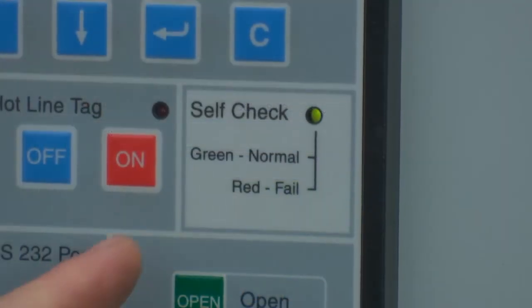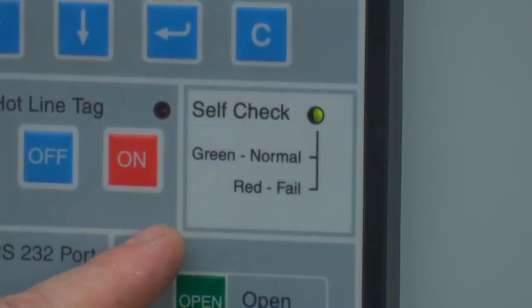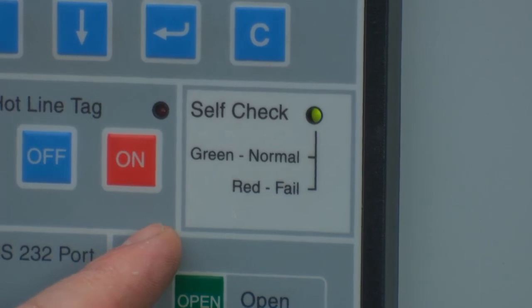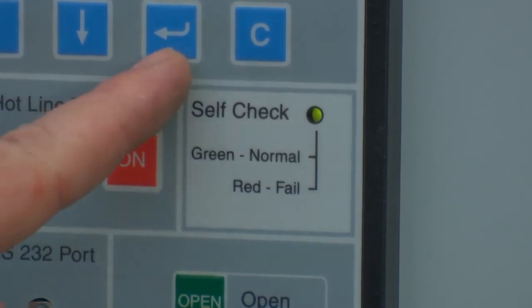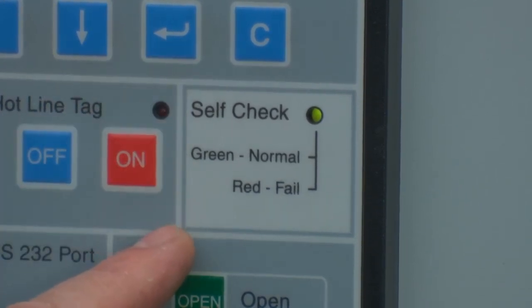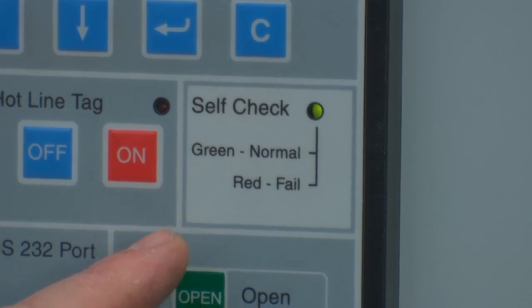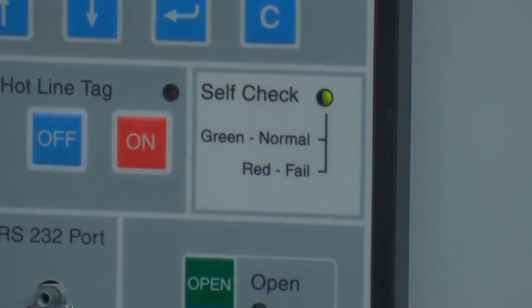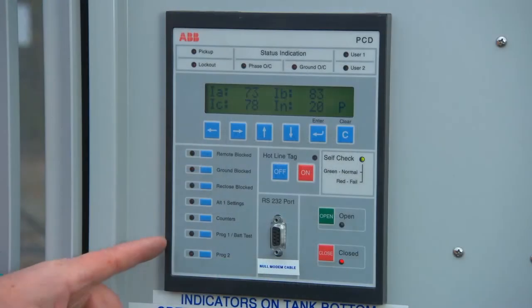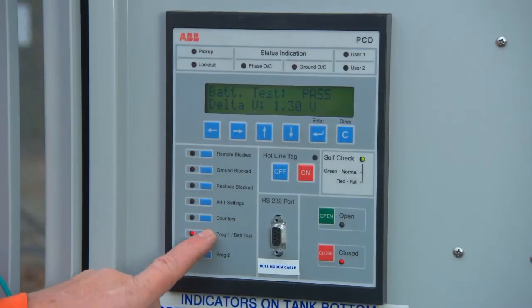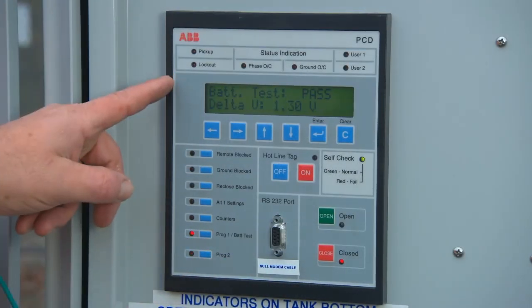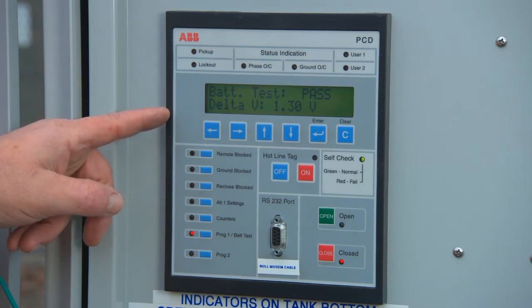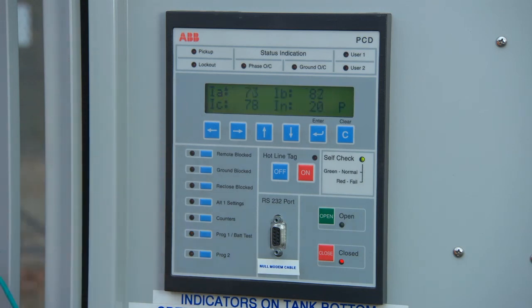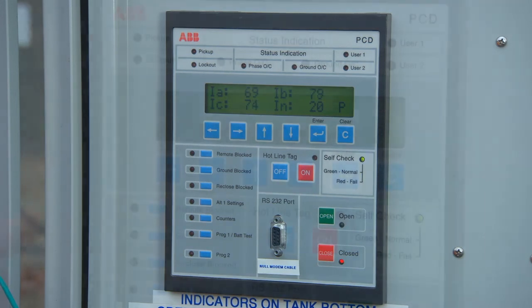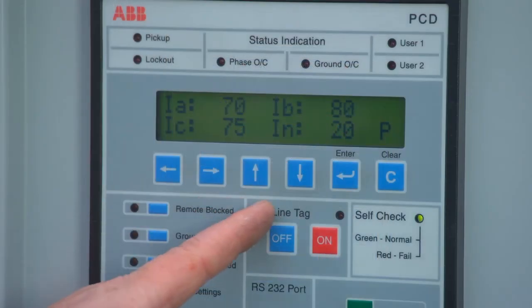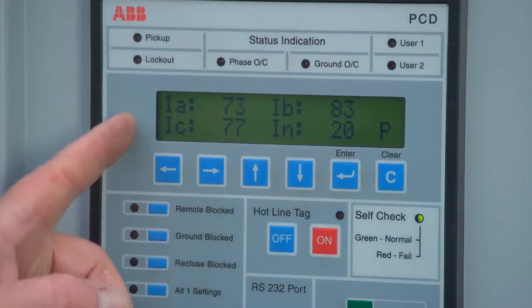Self-check. To verify that the control is functioning properly, every hour or after pressing the Enter button, this unit will perform a self-check diagnostic. A green LED will indicate the unit is functioning properly. Battery test. Pressing this button will perform a battery test. The indicator will turn red. The pass and verified delta voltage will be displayed. The directional arrows will allow you to scroll through selections on the screen.